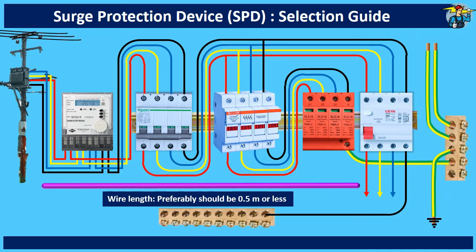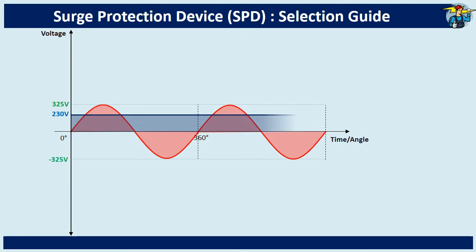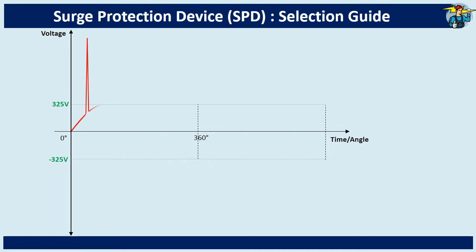To get a clear idea about selecting an SPD, let's first look at how transient voltage spikes appear in the voltage sine wave. This is a 230 volt, 50 hertz frequency AC supply, where the actual voltage alternates between a maximum of 325 volts and a minimum of minus 325 volts respectively. As this alternation works very fast, with a speed of 50 cycles per second, we take this voltage as the maximum continuous voltage of 230 volts — that is the RMS or root mean square value. Here shows how the sudden voltage spikes appear in the voltage sine wave. These will reach a high peak value, but disappear quickly.